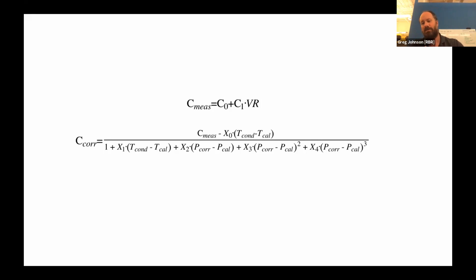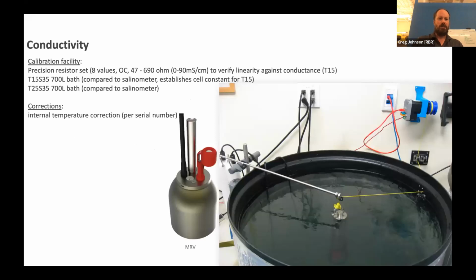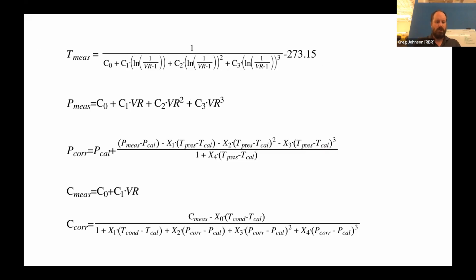Now, in a lab, we always do our calibration at atmospheric pressure. But if you'd like to calibrate your sensor at 4,000 meters against a bottle that you pulled from back there, you can absolutely do so. You only need that single point. And that, I think, is really the sum total of temperature, pressure, and conductivity calibration here at RBR.